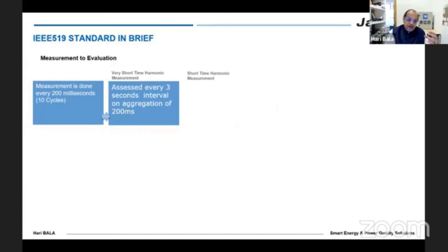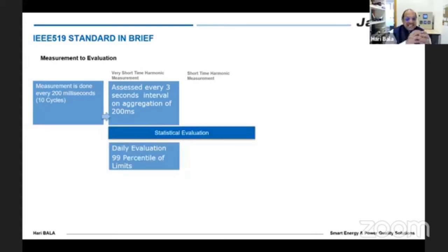The standard IEEE 519 is asking us to measure readings every 200 milliseconds and average that, aggregate it over 3 seconds and put it in one box, as I present over here. And then these 3-second values are evaluated daily for a 99 percentile of limit. So it means you will have roughly 28,800 samples of data in one day for individual harmonics, say 1 to 50, plus TDD, and it asks us to collect all the data and put it down for daily evaluation against certain limits.